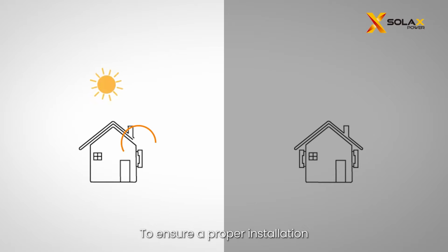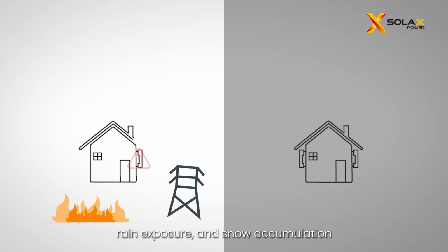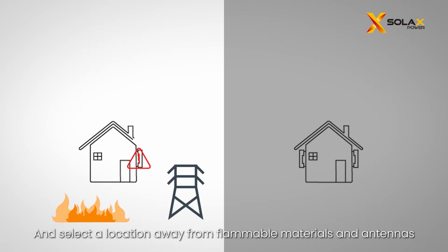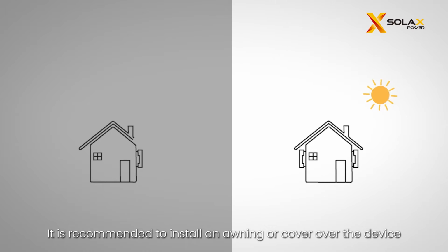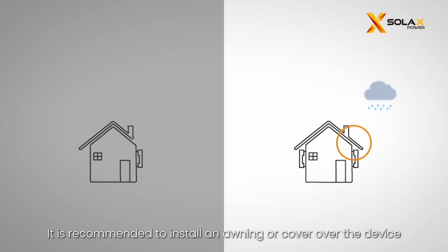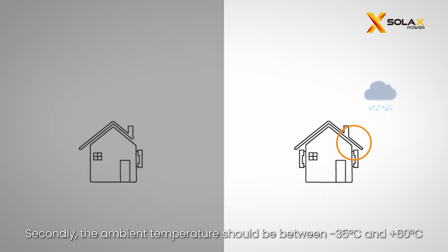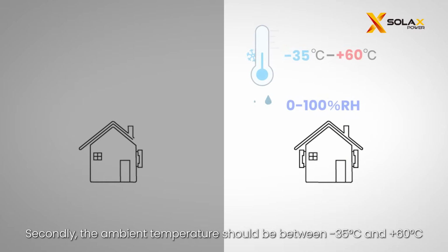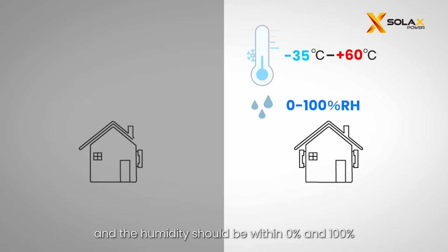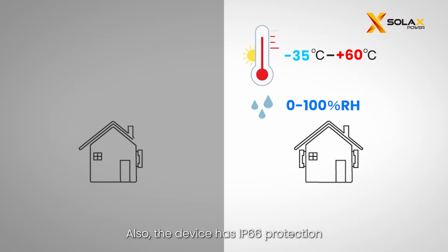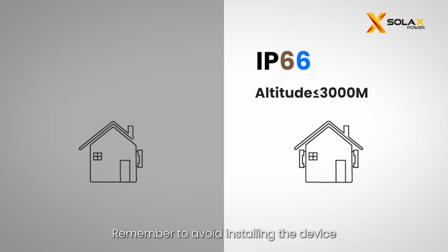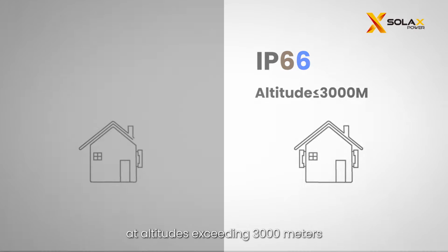To ensure a proper installation, please follow the guidelines. Firstly, please avoid direct sunlight, rain exposure, and snow accumulation, and select a location away from flammable materials and antennas. It is recommended to install an awning or cover over the device. Secondly, the ambient temperature should be between -35 degrees Celsius and +60 degrees Celsius, and the humidity should be within 0% and 100%. Also, the device has IP66 protection. Remember to avoid installing the device at altitudes exceeding 3,000 meters.